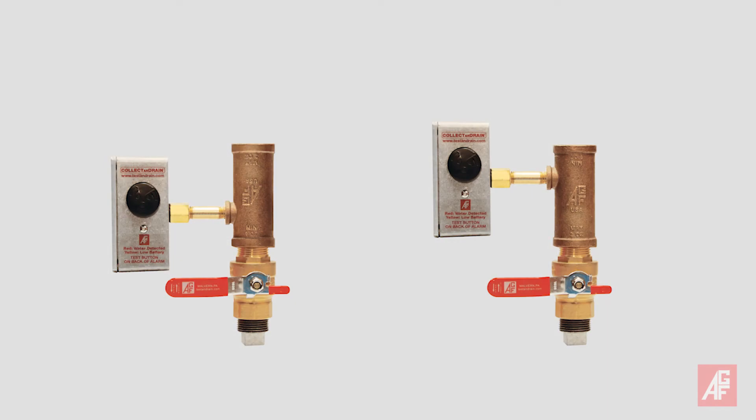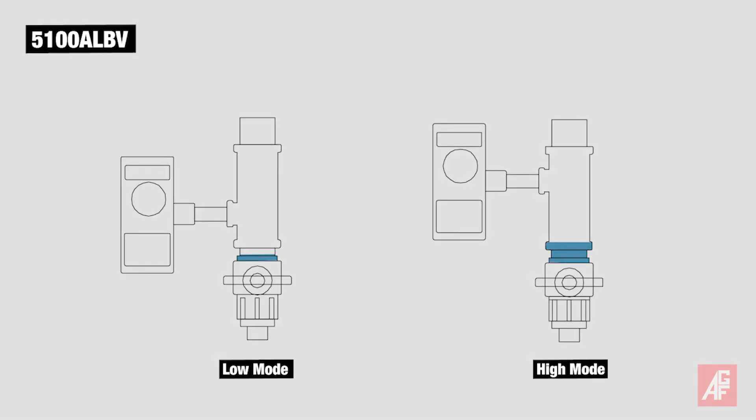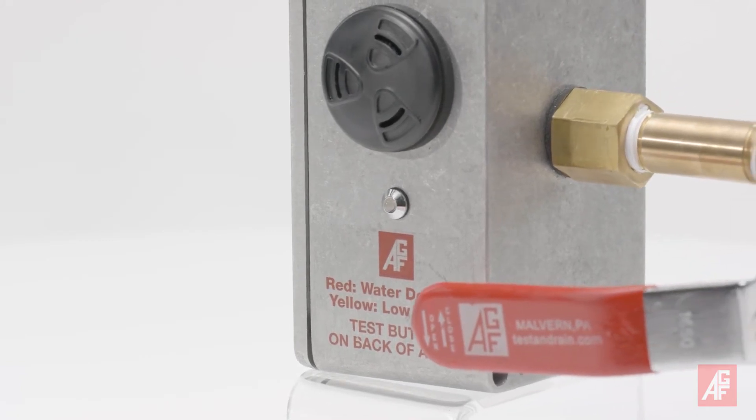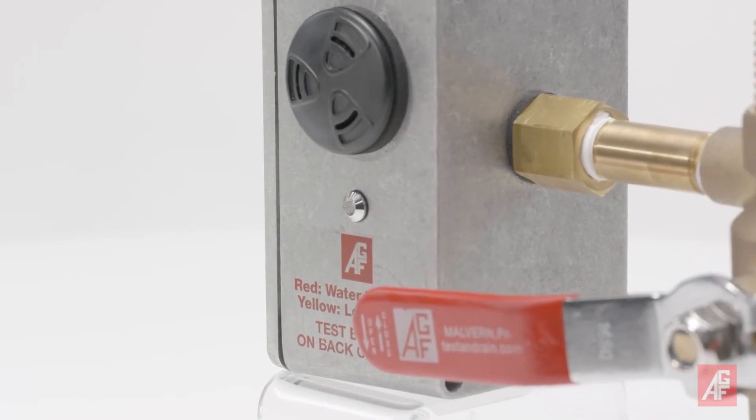The 5100ALBV features a reversible T that lets you customize when the alarm will sound based on the amount of accumulated water. Both models have a customer-enabled temperature sensor that prevents the alarm from sounding when water is present above 45 degrees Fahrenheit.